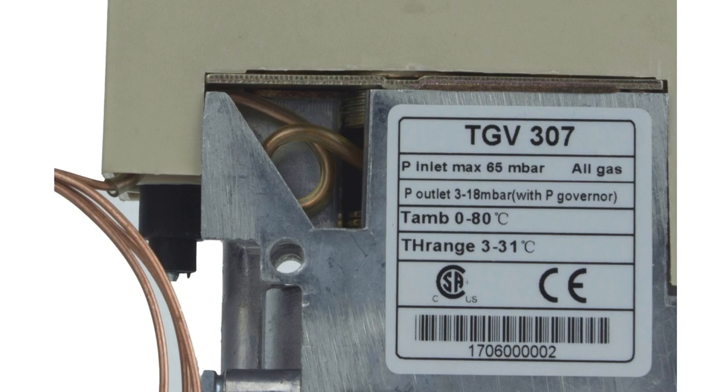You look at the manufacturer's instructions, and it will tell you, okay, if you've got a house with 5 radiators, then you need to have 14 millibars. If you have a house with 3 radiators, you only need 10 millibars. And you adjust the pressure according to the MIs and the situation of your house.